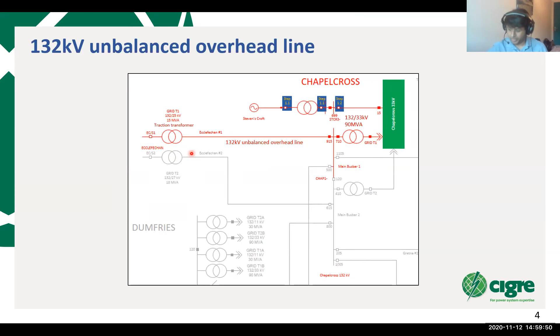Everything shown in red will be energized, and the rest of the network remains de-energized. Now, as you can see, we have quite a few options to restore this part of the network. We can either go for simultaneous energization of the grid transformer, the unbalanced 132 kV overhead line, and the traction transformer altogether, or we can do them separately, or we can consider energizing a primary substation before energizing these bits. So there could be quite a few combinations, and that forms the basis of the different case studies we have studied here. Eight of them are presented here, and they look into the impact of different factors such as energization voltage, point on wave switching of the breaker system, loading condition, and transformer saturation, and how these factors influence the imbalance on the network or overvoltage in the system.